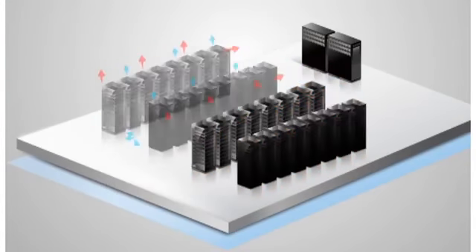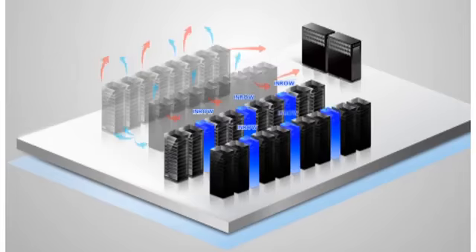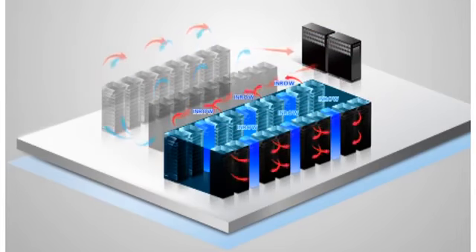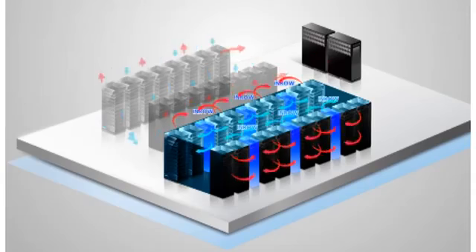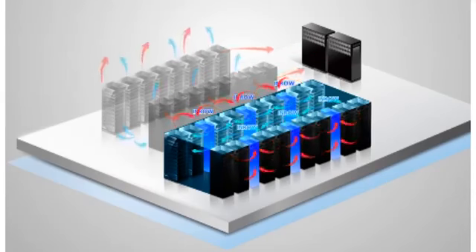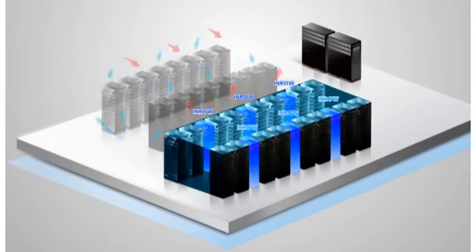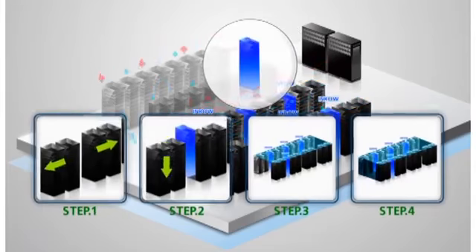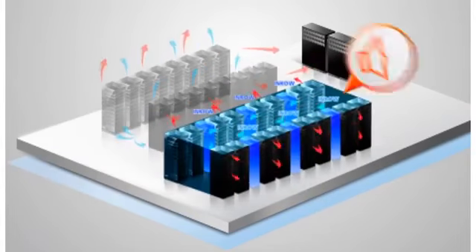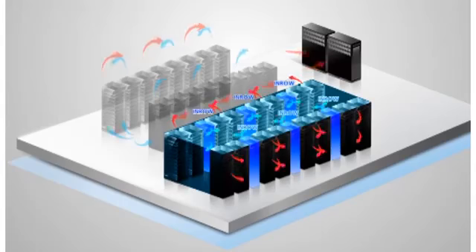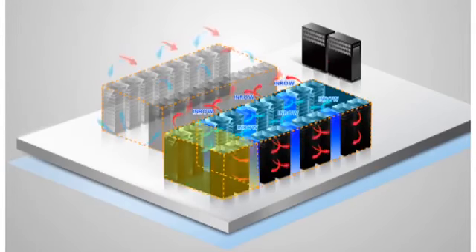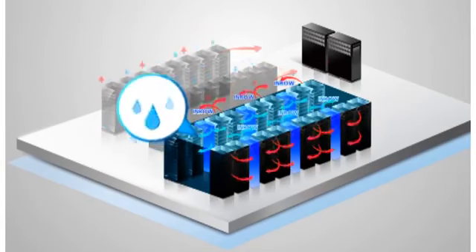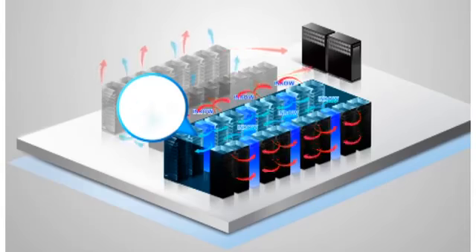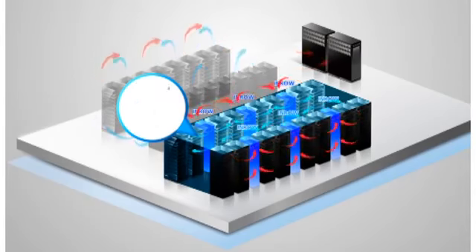To better the efficiency and tackle uneven heat dissipation of high-density racks, the next generation of cooling equipment aimed at cooling the rows to eliminate hotspots. This only partially solved the cooling problem and created new issues. A. Difficult installation. B. Loud equipment. C. The equipment occupies rack space. D. A risk of the air conditioning unit causing water condensation on the server rack.